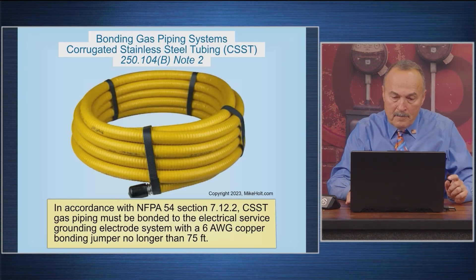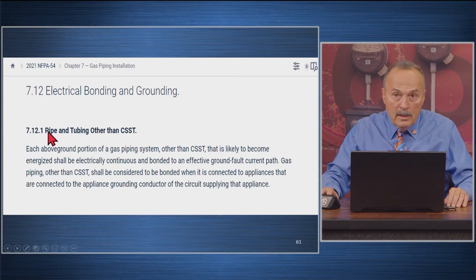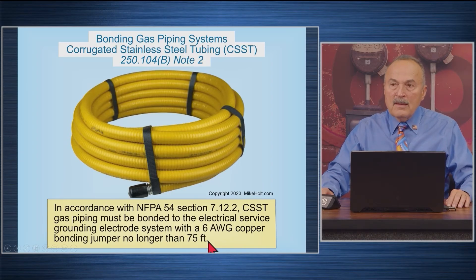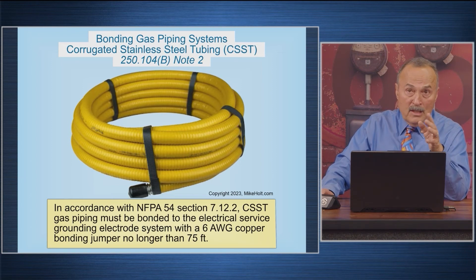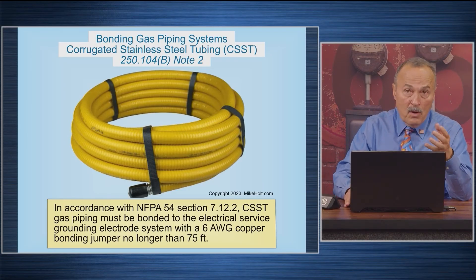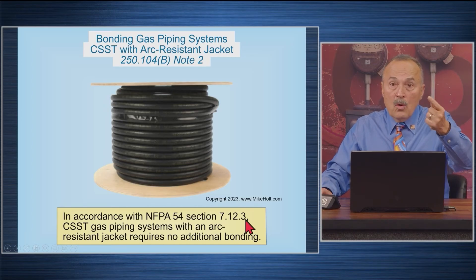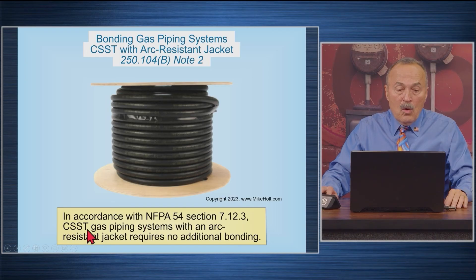Moving on: NFPA 54 7.12.2 states that corrugated stainless steel gas piping must be bonded to the electrical service grounding system with a 6-gauge copper conductor not longer than 75 feet. So if you have CSST, you're going to have to bond it. NFPA 54 7.12.3 states that corrugated stainless steel tubing gas piping systems with an arc-resistant jacket require no additional bonding.